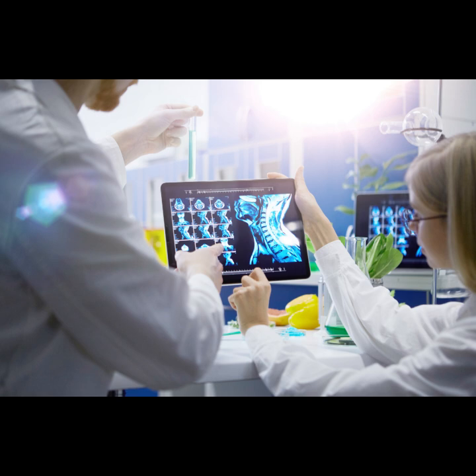Precisely. These are another set of coils, resistive electromagnets, inside the scanner bore. And they can rapidly switch on and off to create a linear variation, a slope in the magnetic field across the imaging volume. A slope in the field strength. Yeah, think of it like a ramp. We can make the field slightly stronger on the left and slightly weaker on the right, for instance. These gradients are measured in units like millitesla per meter, say 20 to 100 mT/m.